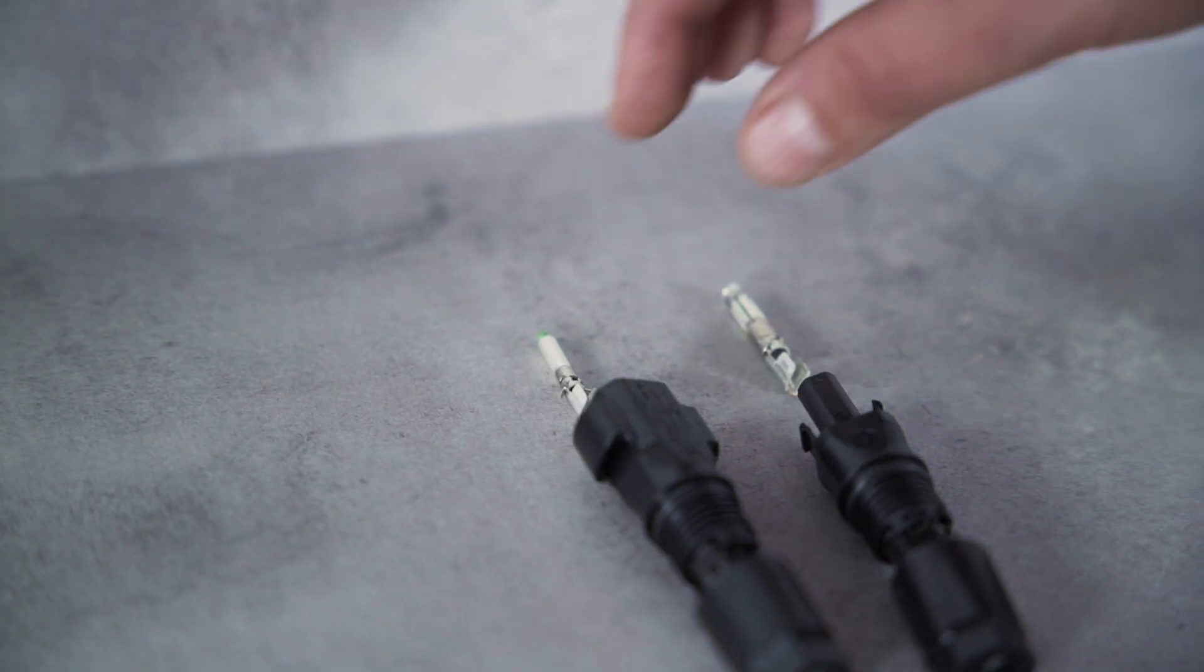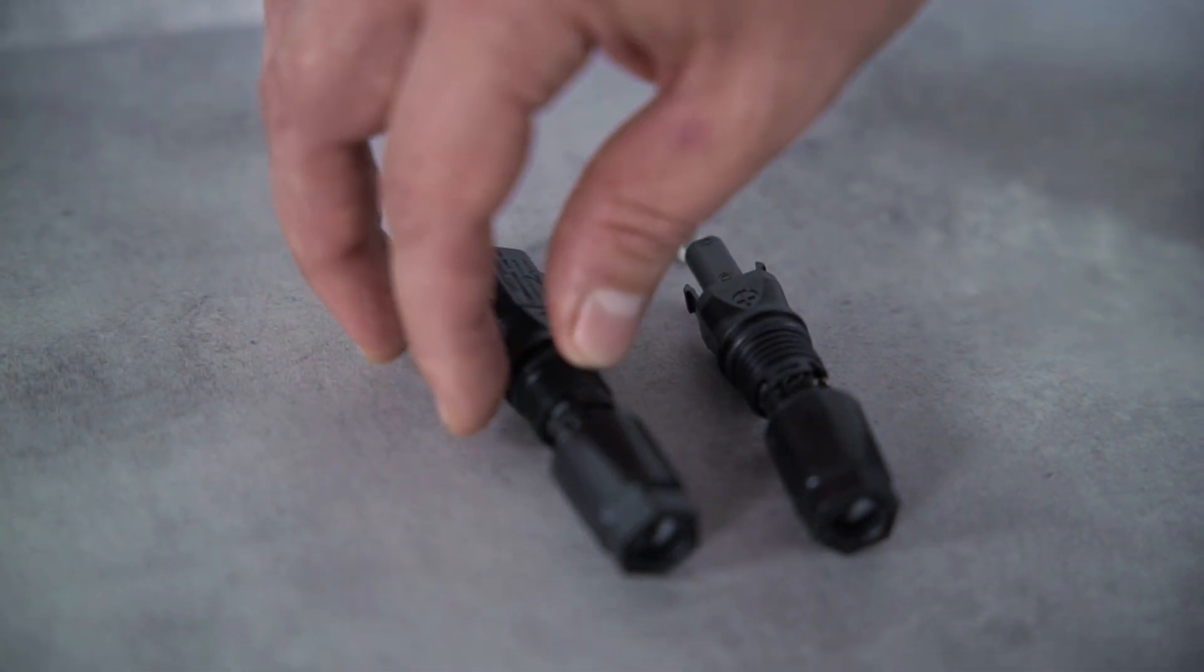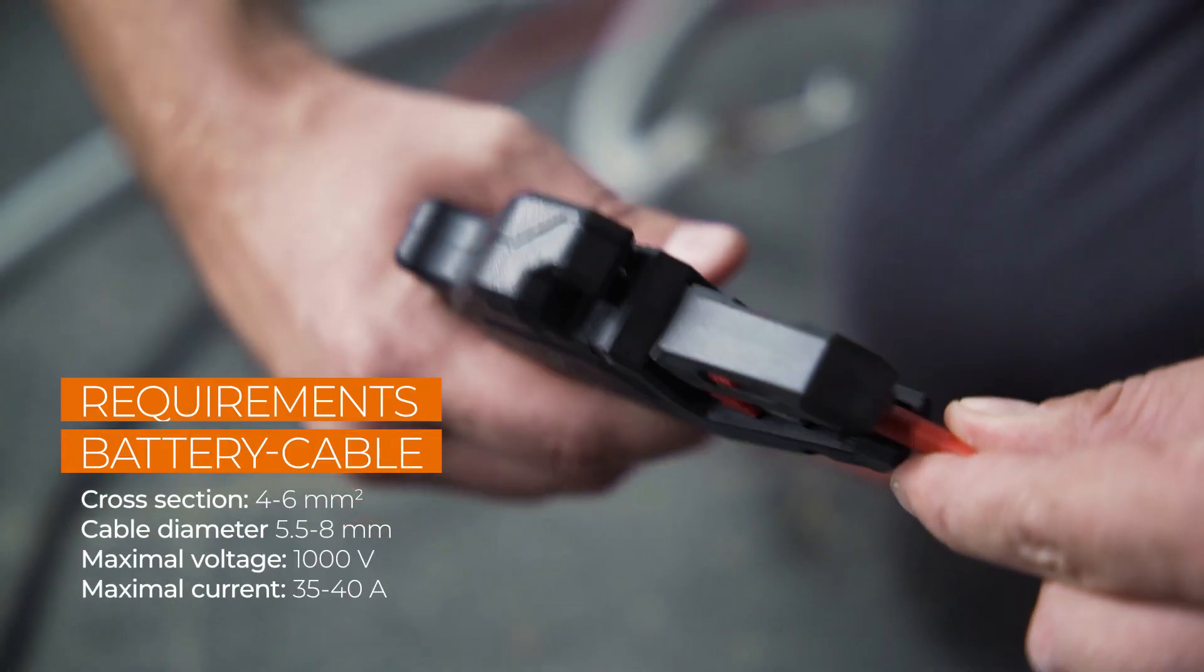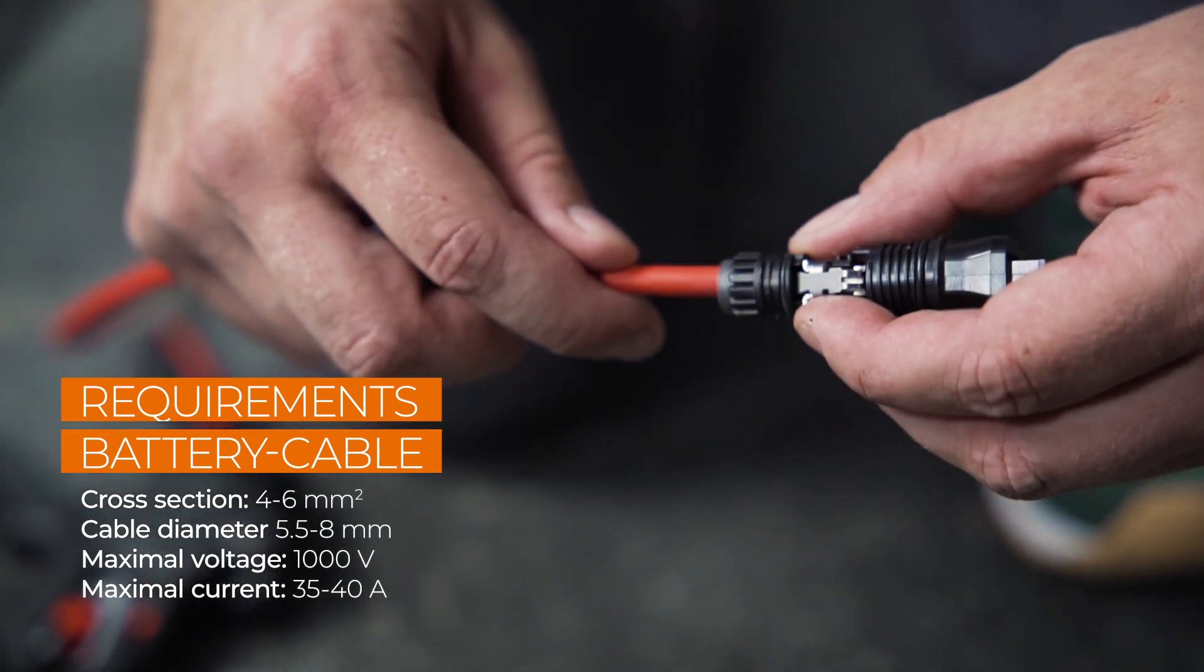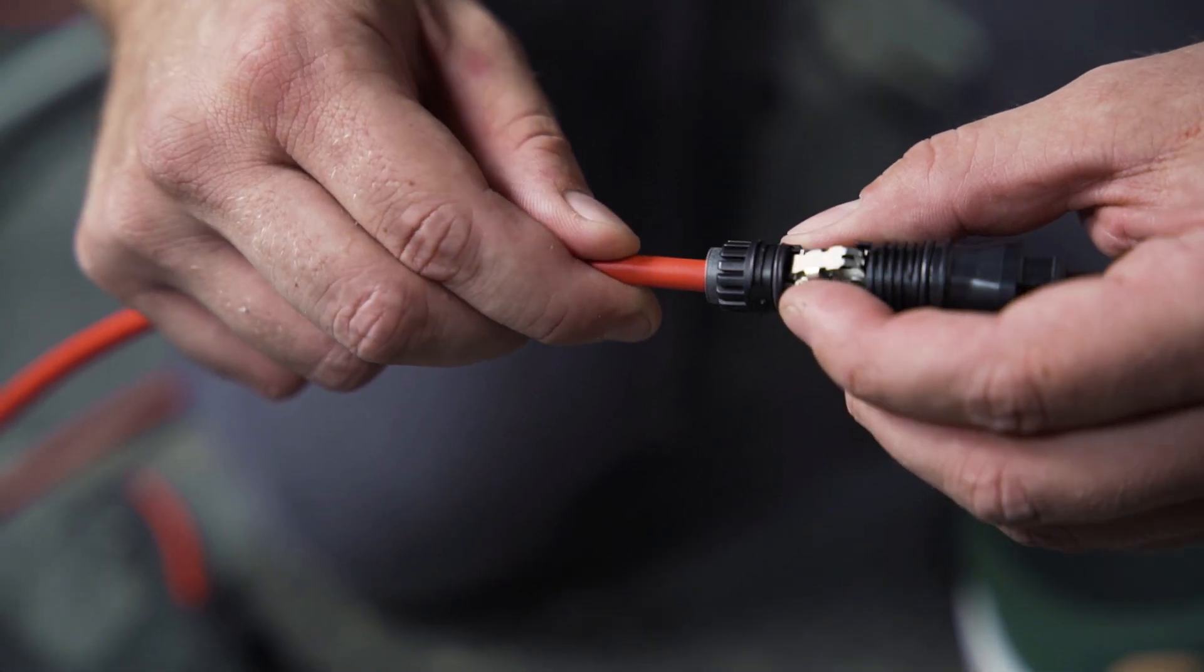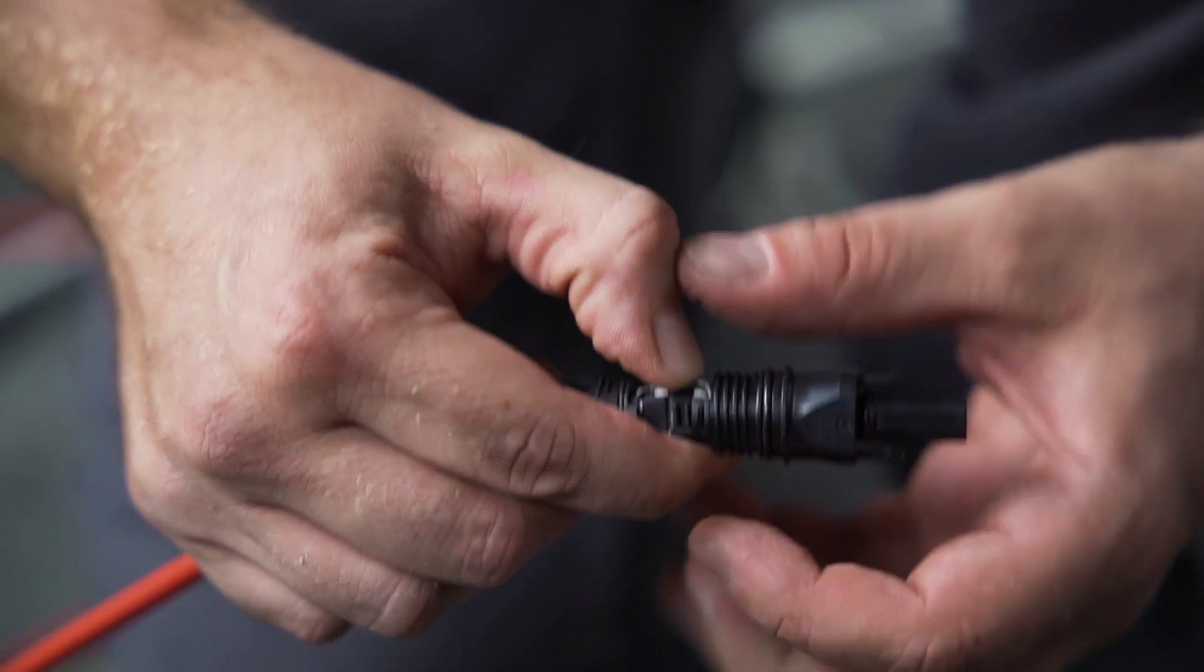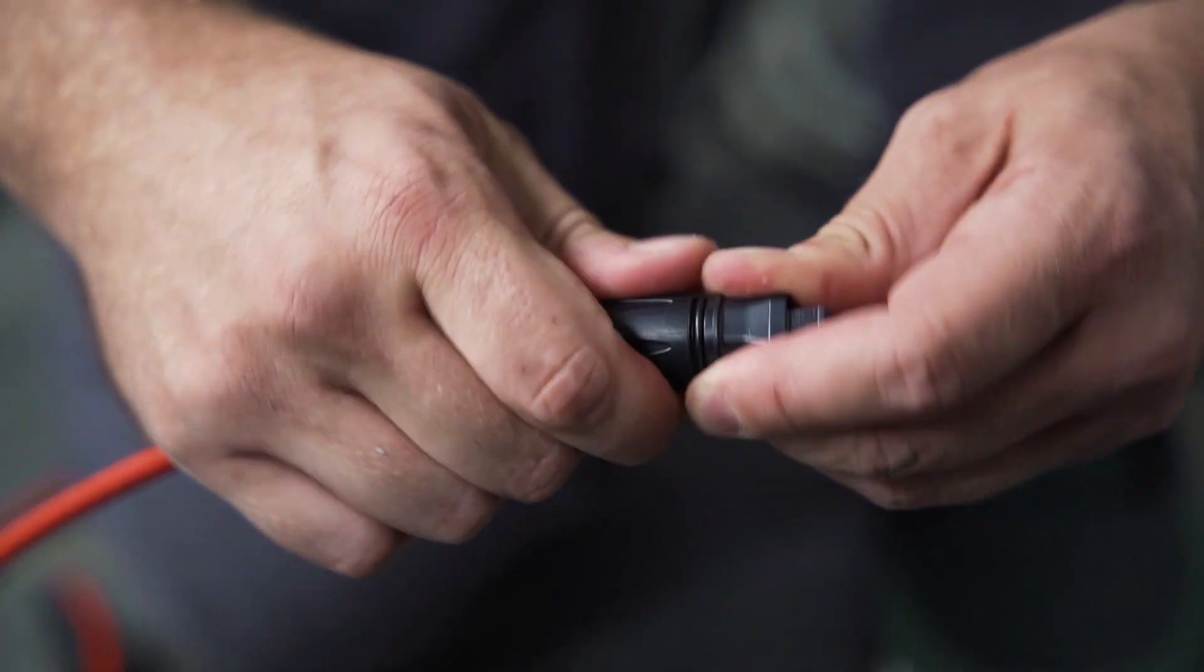Sunclix connectors are used to connect the battery. Pay attention to the correct polarity. This is marked on the inverter. First insert the cable until resistance is felt. Now the cable is fixed to the connector by pushing down the spring. A clear click can be heard when it clicks into place. Tighten the plug, plug it in, that's it.